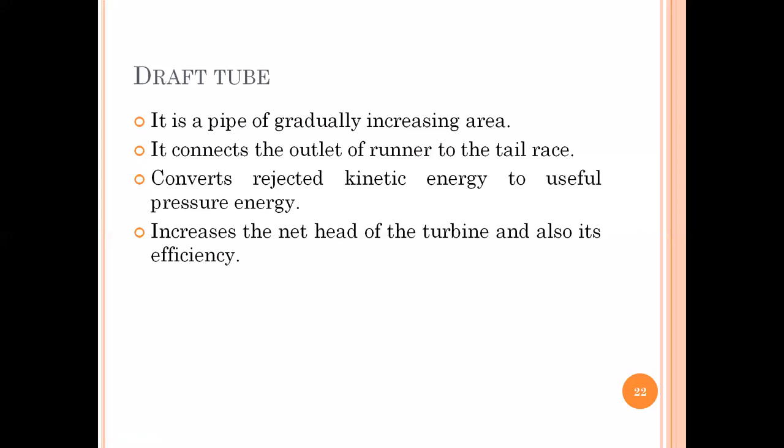Since it's converting kinetic energy to useful pressure energy, it increases the net head of the turbine, and since it's increasing the net head it also increases efficiency. Without a draft tube, the kinetic energy gets rejected and wasted, and at the outlet of the runner negative pressure is created, making water movement another issue.